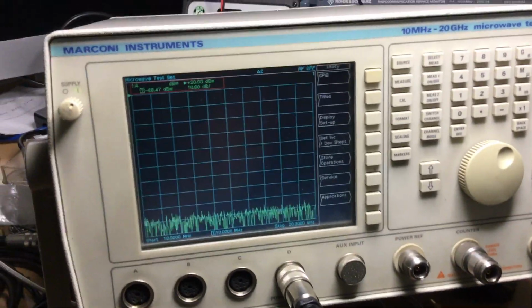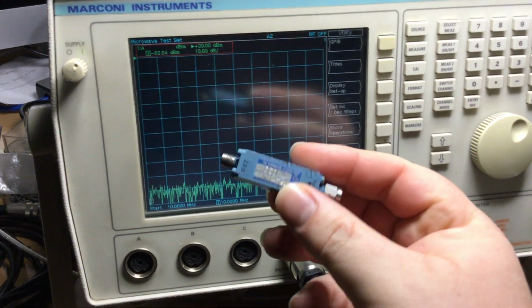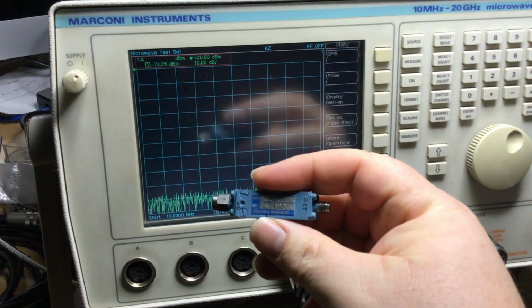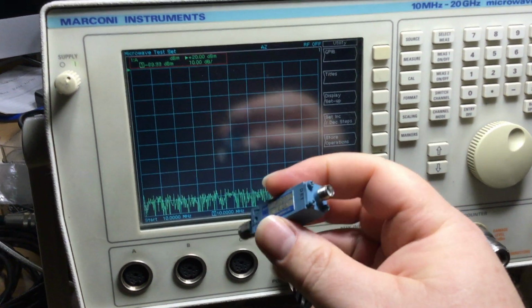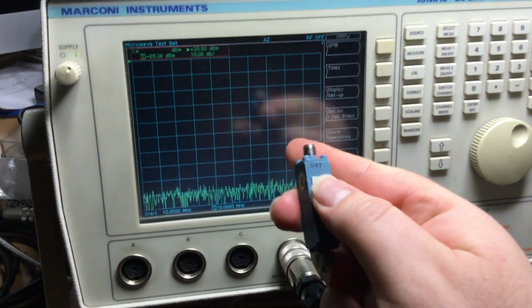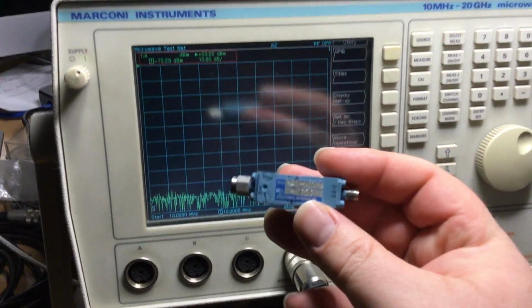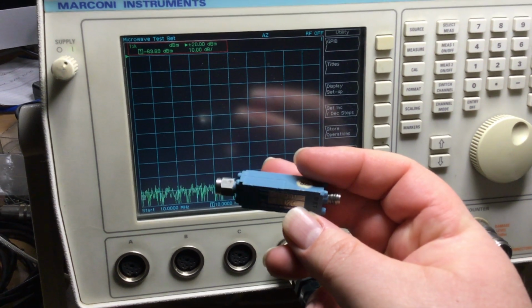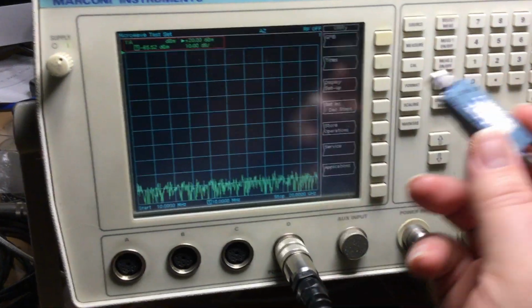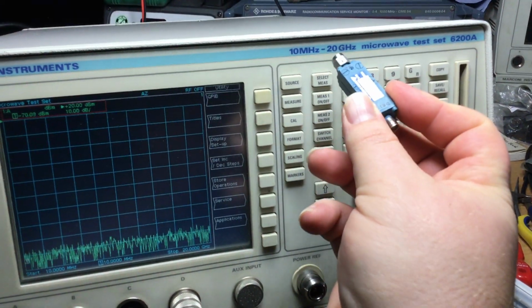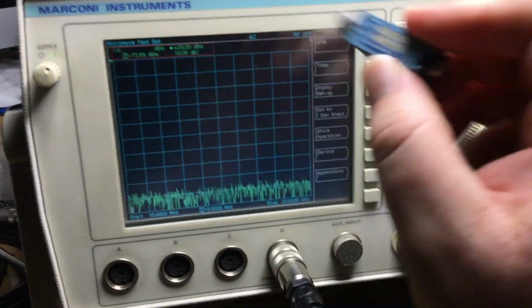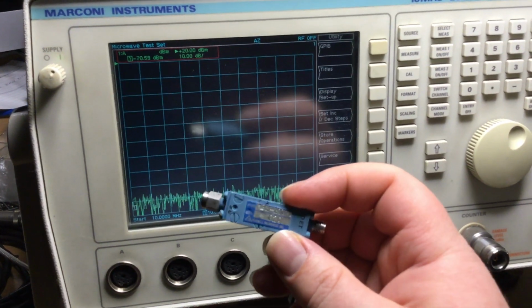If it doesn't work, then I've got another plan, which is to install what I've found here, a proper detector diode module manufactured by a company called Triangle Microwave. It has an SMA output, which is actually a DC output because it says DET there, and this is exactly the same kind of diode as what was in the test set originally, except this one, when I've tested it, cuts off quite sharply around about 18 gigahertz, so I'm not sure if it'll give the right spec over the whole frequency range up to 20 gigahertz. So we can try it anyway. If not, then I'll have to buy the part and simply get on with the repair that way, even though it might be quite expensive.